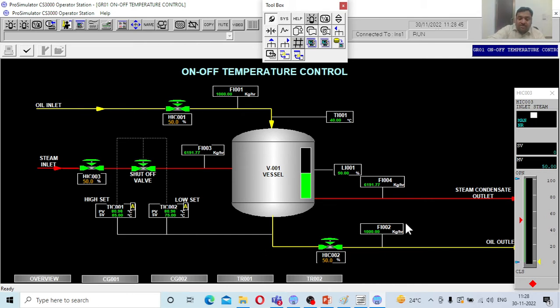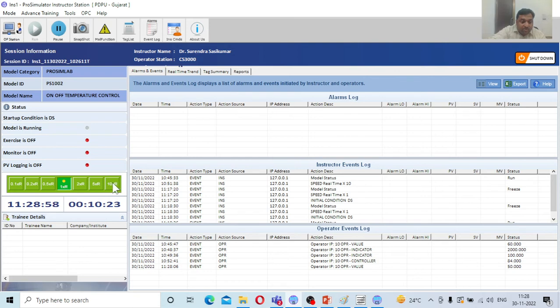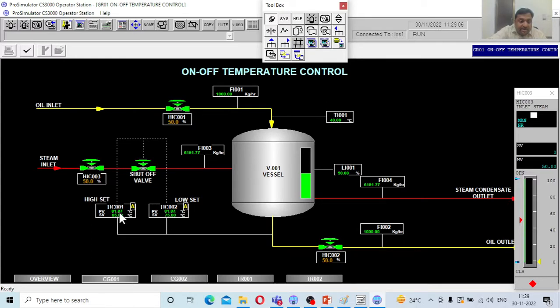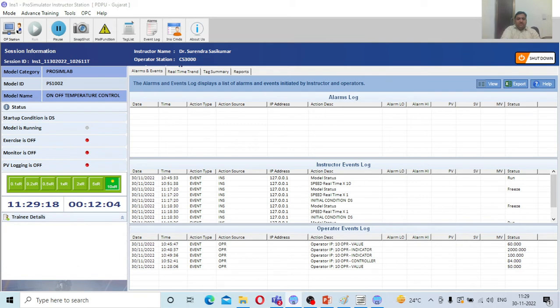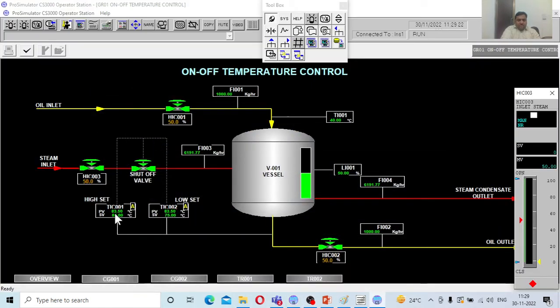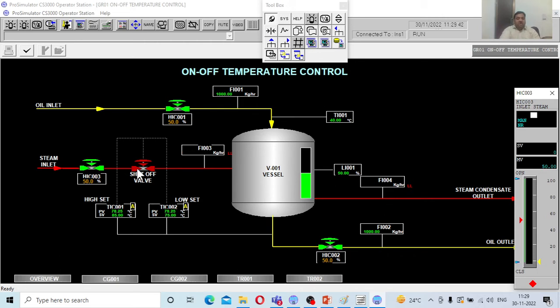It takes time to reach from 81 to 85, so I will increase the simulation speed to about 5 times. You can see the process value rising: 81, 81.7, 81.8 because more steam is going into the jacket. Let me increase to 10 times speed. The process value is now around 83.7 — the moment it hits 85 the valve will be completely shut off. At 84.9 the present value is about to trigger — and now it has hit 85 and the valve is completely shut off.